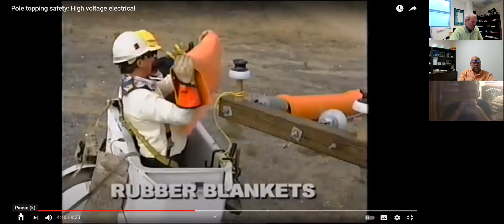500,000... 5,000 volts. I don't know where you're going to get 5,000 volts on a primary line. That's extremely low. This isn't a trick question, but think about it, and keep in mind what we talked about with phase to ground voltages and phase to phase voltages. What kind of rubber glove are you going to use, voltage wise?